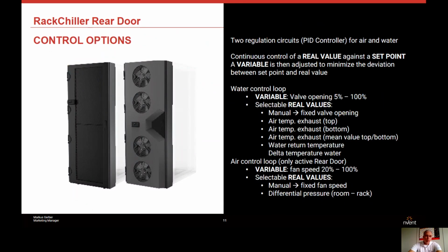It's basically very simple. How these systems operate is you have a set point and then you regulate against the set point. In this case, there is a water circuit, the liquid circuit, and then you choose which temperature you want to have on a stable level. So you can pick, for example, the room temperature at 22 degrees Celsius, and then the water flow is adjusted to keep exactly this temperature in your room.